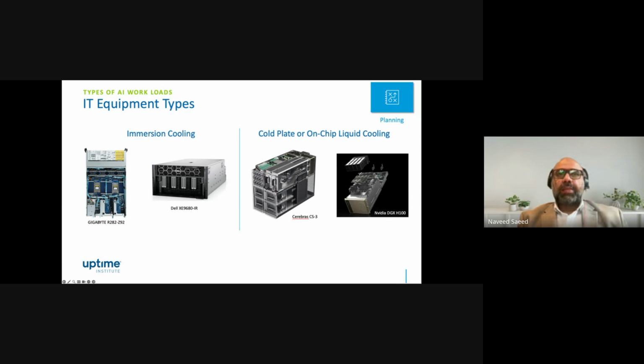In the past, our conventional data centers used air cooling systems, so it doesn't matter which kind of equipment is going to come in. Air is air, and as long as you can deliver air to a specific rack, you can, up to a certain density, support the cooling on those racks. Although there are a lot of challenges, and the people on this call who have been operating those facilities and upgrading IT refresh also see a significant challenge in delivering cold air all the way to specific racks, especially the higher density racks, around 20-25 kilowatts per rack. But in this case, it is more specific and more particular. So designing a facility, knowing the racks, how to deliver the liquid all the way, and how to remove the heat from each kind of server is very important, because without the right design, it will not be possible to place any server in any rack or in any immersion tank.